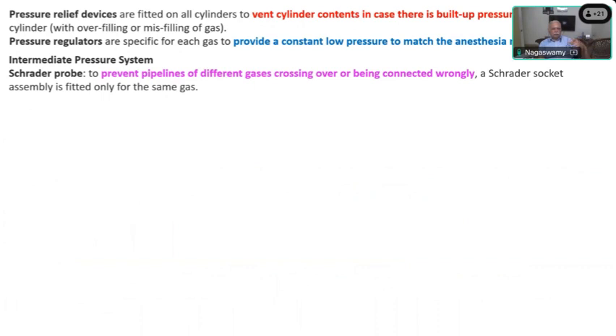Of course, in the high pressure system, the Schrader probe is given to prevent the pipeline from being fitted. Schrader is introduced here because the pipeline pressure coming is only about 50 to 60 psi, whereas the gas cylinders which are attached to the machine and opened are at 1500 to 2000 for oxygen and 750 for nitrous oxide. So that comes under high pressure. Whereas the pipelines, even though books all show them under the high pressure system, at that level it's only an intermediate pressure system.